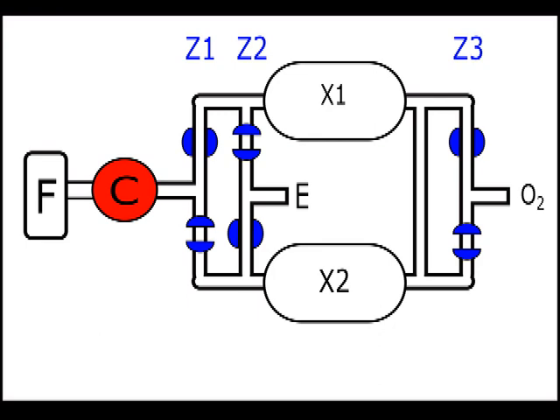The dust-free air coming out from the compressor enters a cartridge labeled here as X1. Inside the cartridge, there is a substance known as zeolite, which is made of porous crystals and acts as a sieve. Since oxygen has a slightly smaller molecular size than nitrogen, it allows oxygen to go through and stops nitrogen.